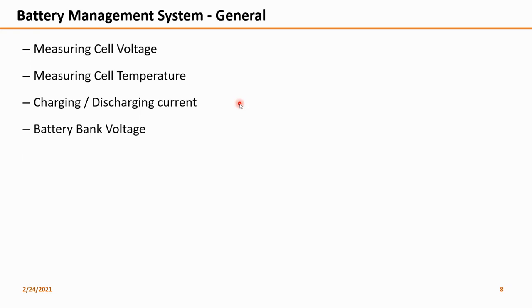Based on the industry, they will measure the cell voltage because this is the main parameter to monitor the battery. The battery may open, or the voltage may be lesser because of a change in chemical parameters inside the battery. If a technician doesn't monitor this cell voltage properly, it could be a catastrophic failure for the total battery management system.